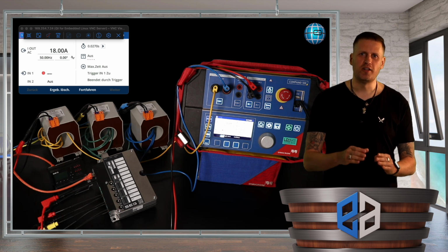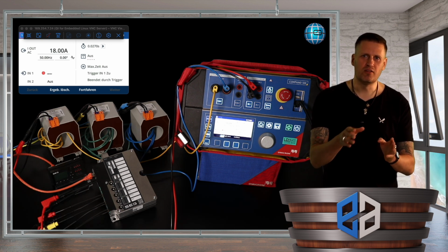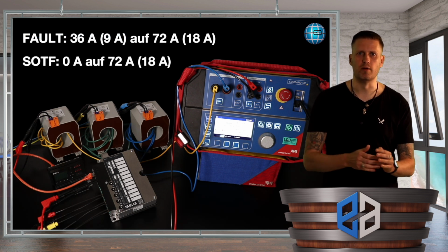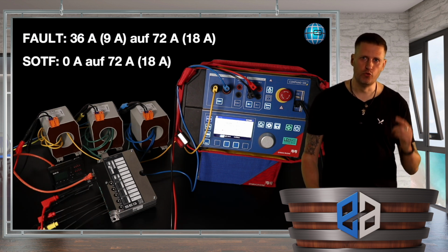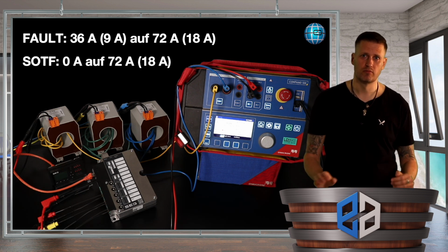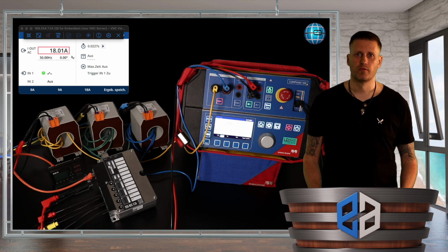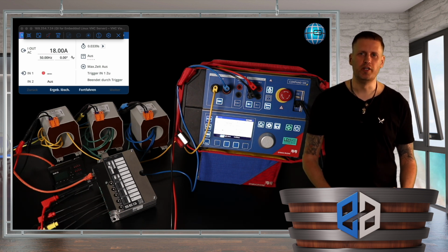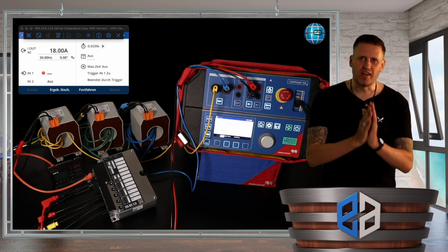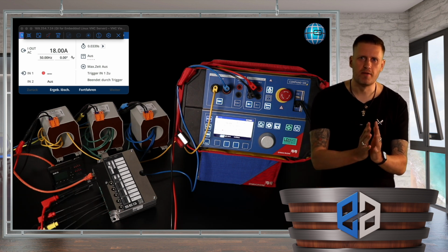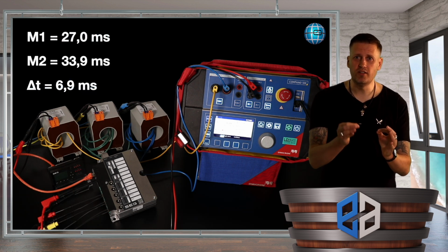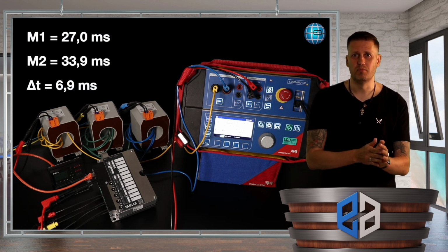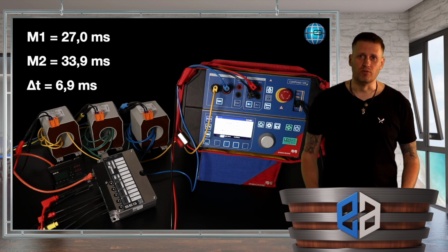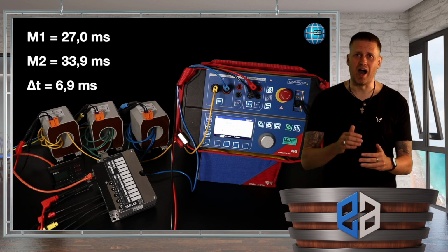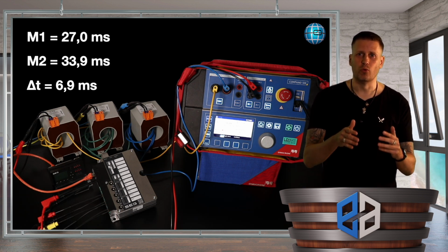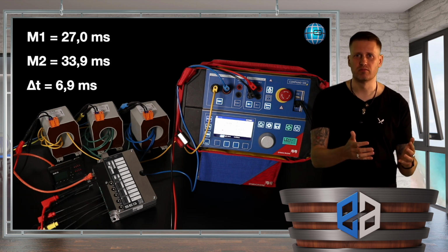We measure a time of 27 milliseconds and now repeat the test with a jump from 0 amps to 72 amps, or of course to 18 amps. You remember the 4-fold winding of the CTs. And get a time of 33.9 milliseconds. Standing ovations, ladies and gentlemen. The difference between these two release times is just 6.9 milliseconds. From my point of view, this is absolutely amazing because in our current example, the relay boots within less than half of a mains period. That's damn fast.